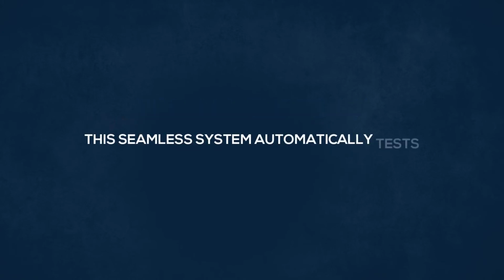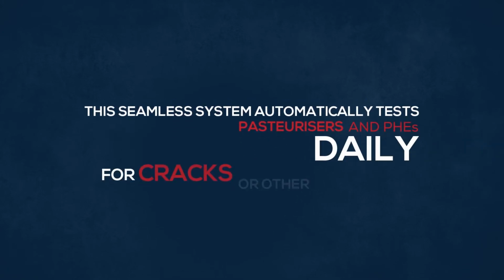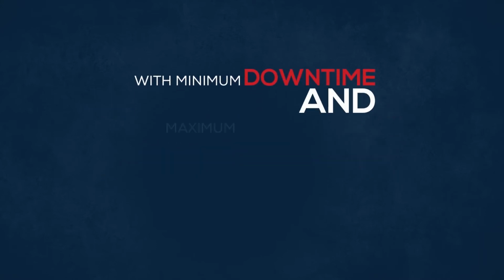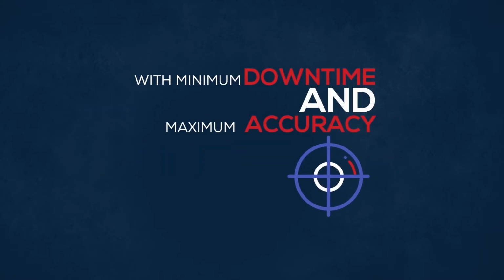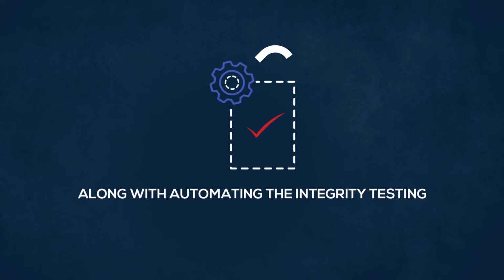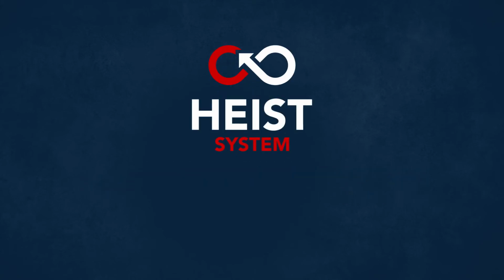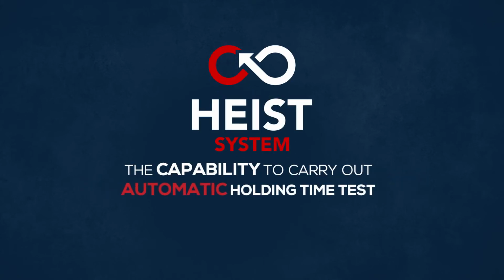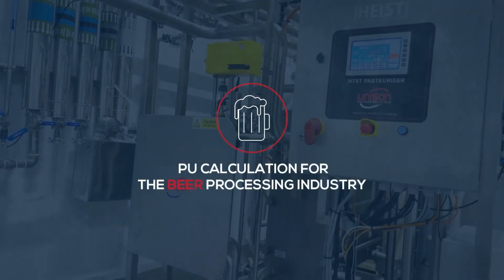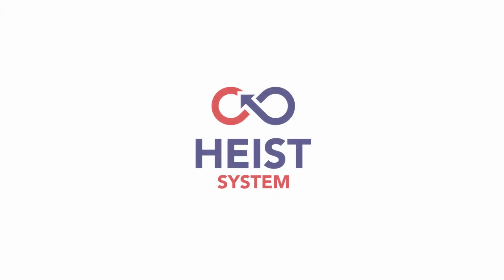This seamless system automatically tests pasteurizers and plate heat exchangers daily for cracks or other defects with minimum downtime and maximum accuracy. Along with automating the integrity testing, HEIST also has the capability to carry out automatic holding time tests and PU calculation for the beer processing industry.